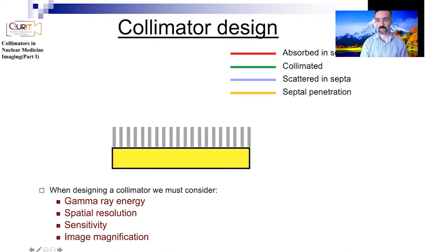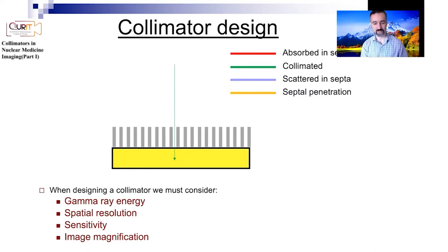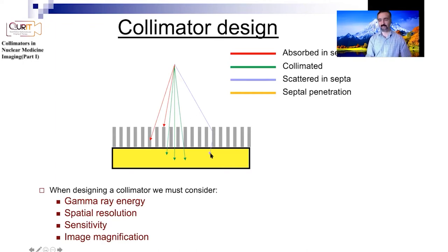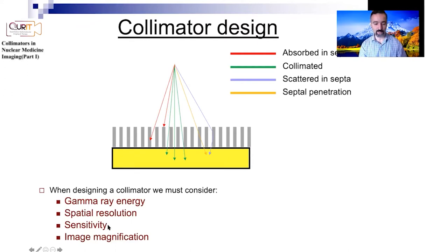There are four kinds of events to consider. First, an event that has been properly collimated and successfully detected. Even at angles somewhat different from 90 degrees, photons can still pass through — and the length of the septa (how tall it is) changes the acceptance angle and therefore the sensitivity. Some events are absorbed in the septa. It is also possible for a photon to scatter and be detected — an undesirable event that results in blurring — and in a small subset of events photons literally pass through the septa.